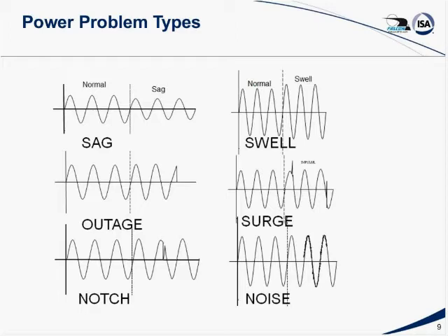More important to many of us are the impulses or transients, if you will, sometimes called surges, and they come in different forms. These are generally a subcycle disturbance, usually a sharp, brief discontinuity of the waveform of either polarity, and it may be additive or subtractive on the nominal waveform. We saw several of them in there. Sometimes these pulses will actually be ringing signals, a damped wave riding on one of the wave shapes, and they, of course, will cause numerous problems.